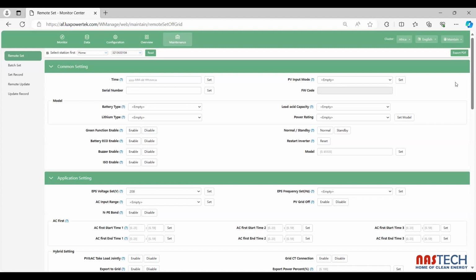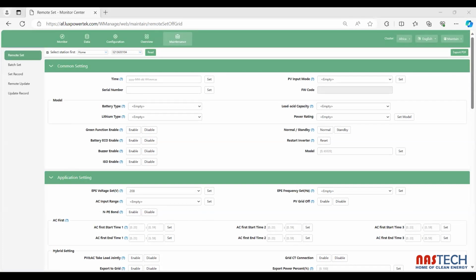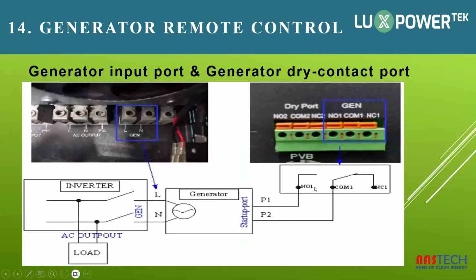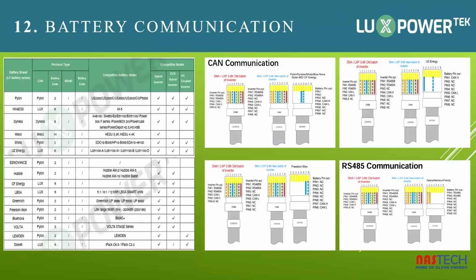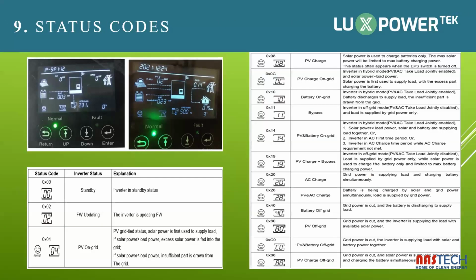These are simple things, of course, but the installer has to set it up at the beginning, and especially with the battery, it is something we really need to focus on, especially for new customers. But one thing that is not clear to me: you mentioned that we need to connect the battery first, but there is also a setting for the battery. How does it work? We connect the battery to give electricity to the device to boot it up. But then for the same battery, we also need to tell the inverter that there is a setting for the voltage, etc. So do you mean that we connect the battery first to the grid port just to power it up, or to the battery port?